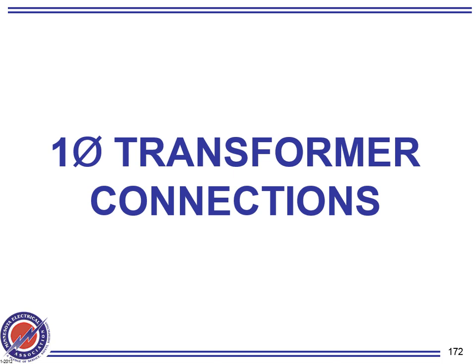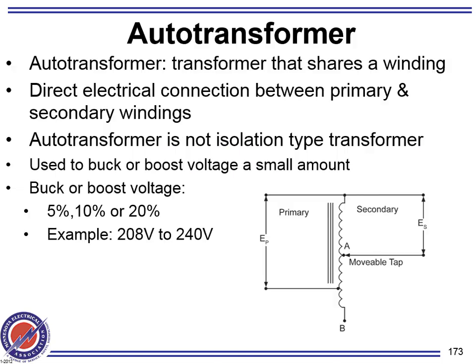Okay, the second thing that we're going to talk about, guys, is buck boost transformers. Equipment, guys, must match. Now, what happens if there's a gap? If the gap is up to 20%, you can bridge that gap between the voltage. You can have a buck boost transformer, a tiny little dude that can bring the voltage of the equipment up to the voltage of the system.